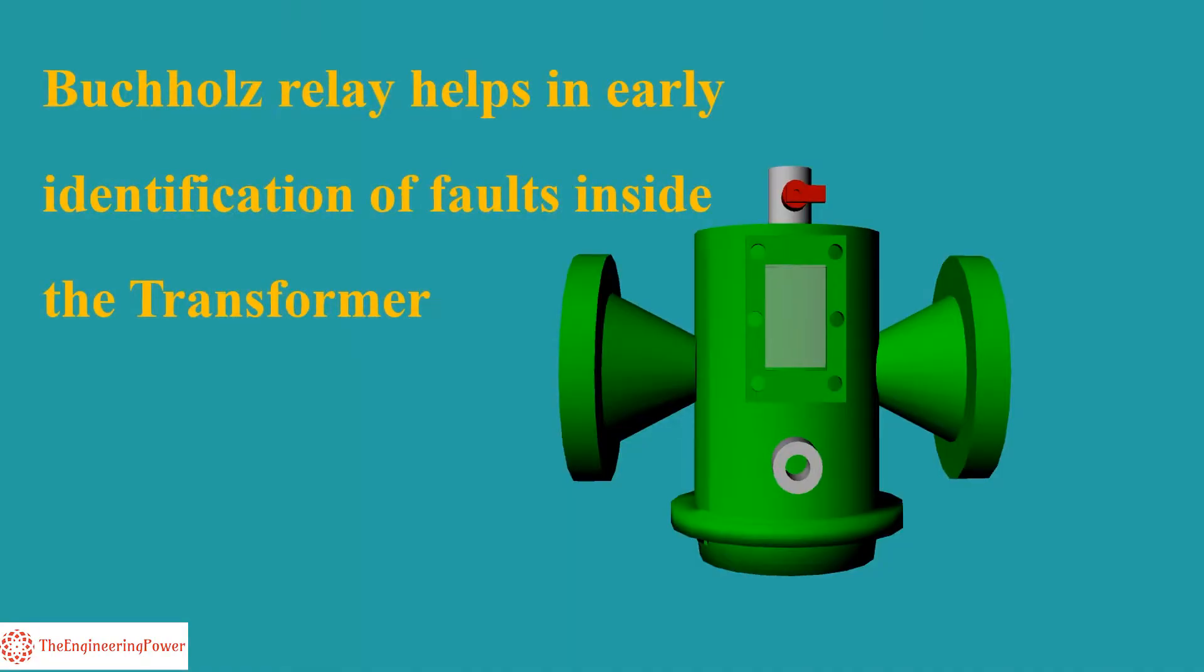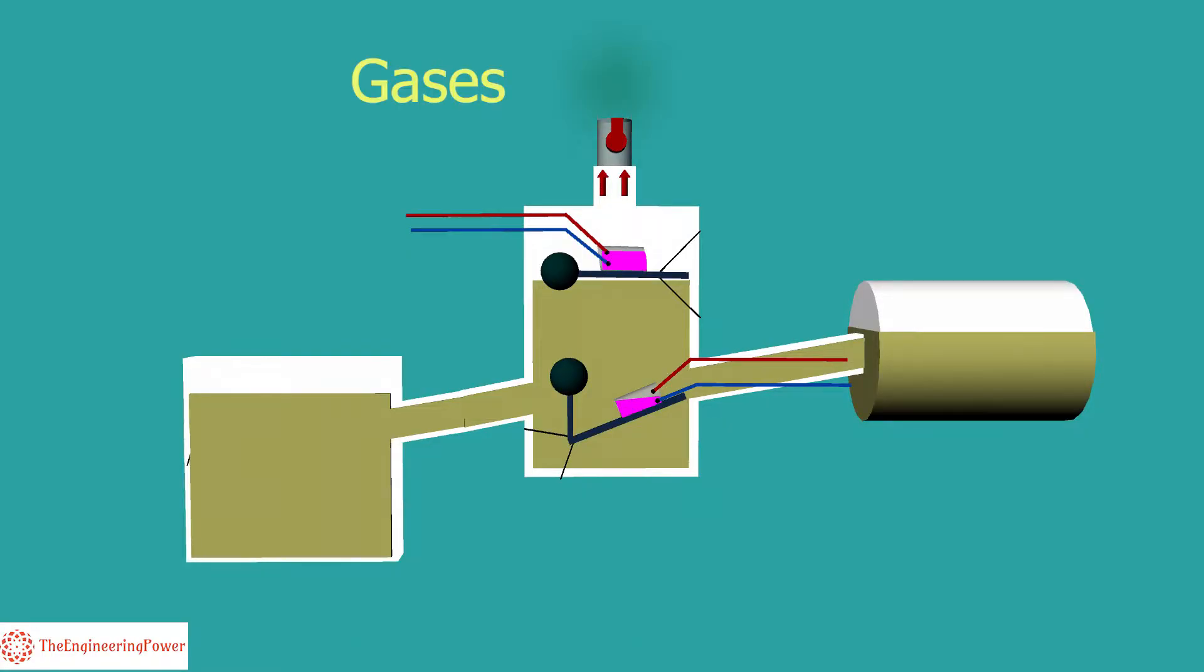Buchholz relay helps in early identification of faults inside the transformer. By analyzing the gases collected from the Buchholz relay, the exact nature of the transformer internal faults can be determined and preventive maintenance can be carried out accordingly, hence helping in prevention from serious faults.